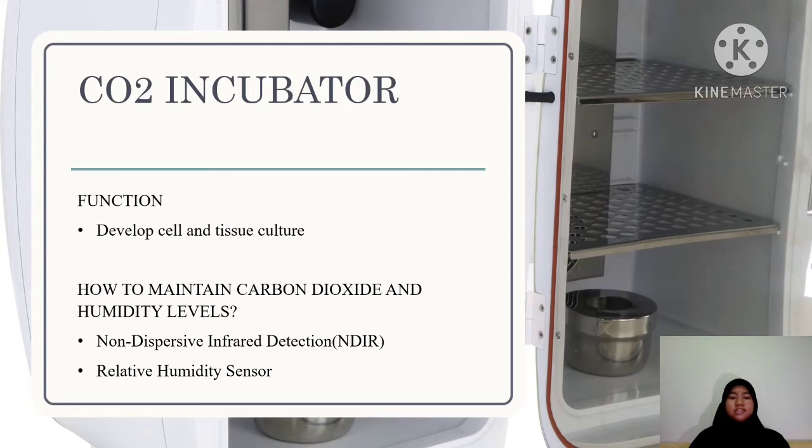To maintain that, it needs non-dispersive infrared detection, which is NDIR. It detects gas wavelength and gets the target concentration of the gas. This is how NDIR controls the carbon dioxide level.